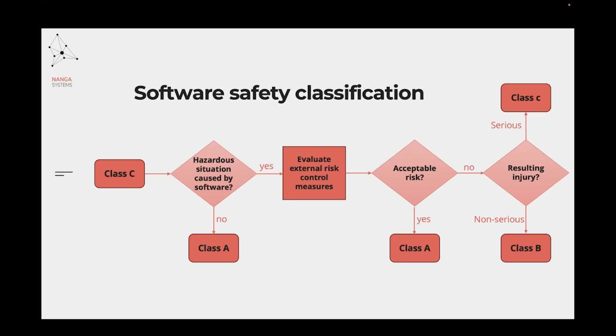In case of acceptable risks, the classification is going to be class A. In case the answer to this evaluation is no, then we have to determine whether the resulting injury is non-serious or serious. In case of non-serious injuries, our software is going to be classified as class B. In case of serious injuries or death, the resulting classification is class C.